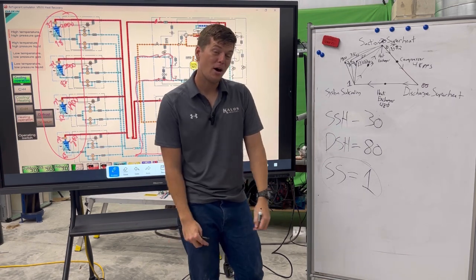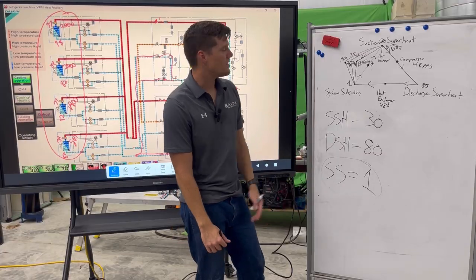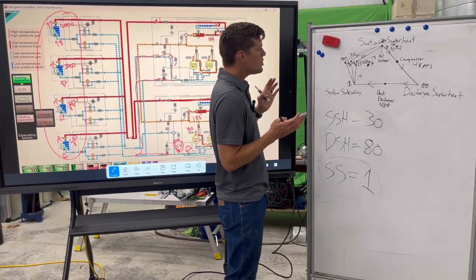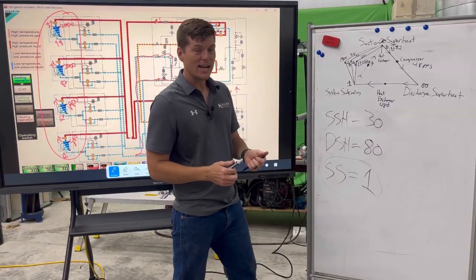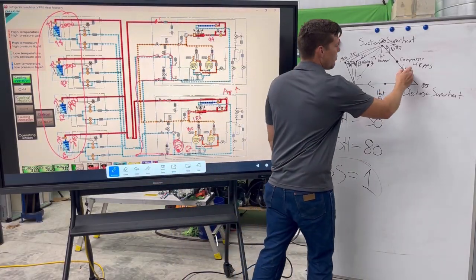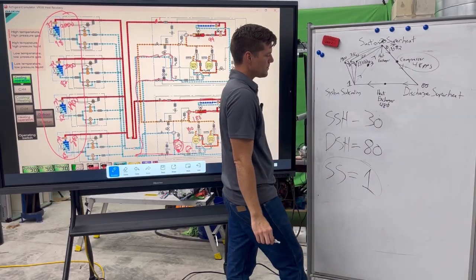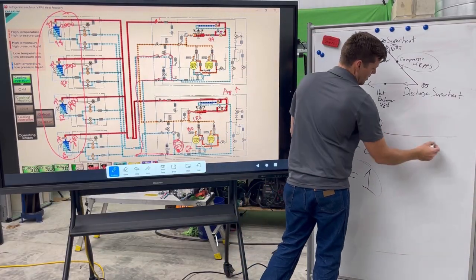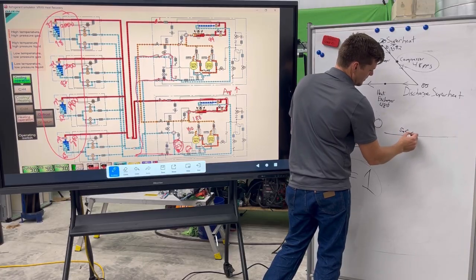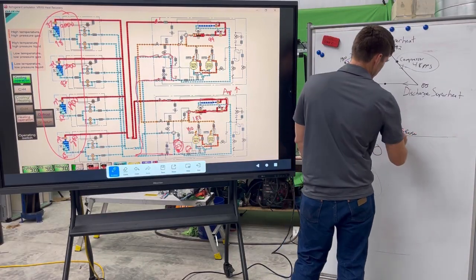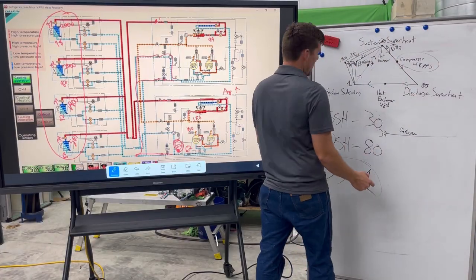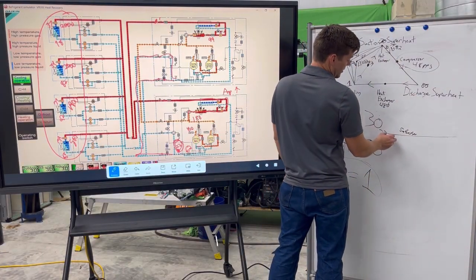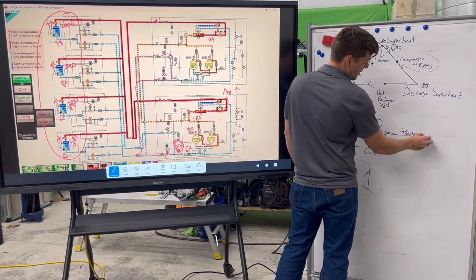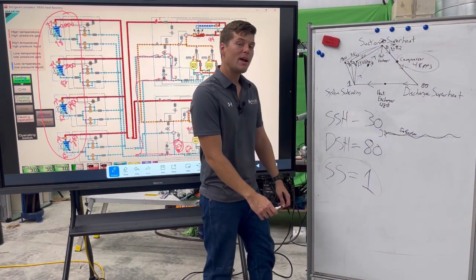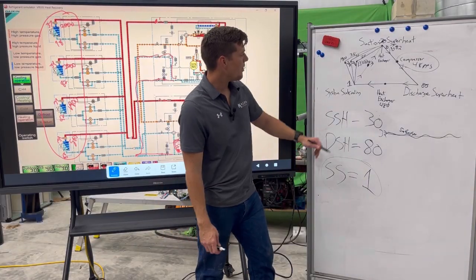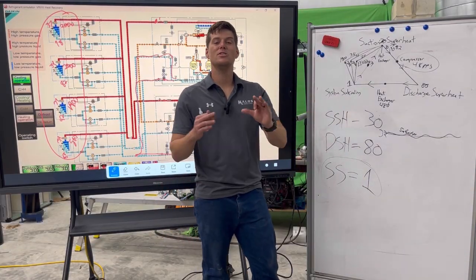Well, why doesn't the system just ramp up to maintain temperature on the indoor units? The indoor units need more liquid refrigerant. Why can't they just go and get it? Well, the reason is because it's running at 48 RPS. Why isn't it running full speed? Because you have to remember that on this chart is a saturation temperature. What is that saturation temperature? It's 32 degrees, so this line is 32 degrees. Where's my suction pressure at? My target is 32, and guess what? My actual TE is 32. So my compressor is not going to ramp up because it's hit its target. If it's hit its target and this is what it looks like, the system is low on charge.